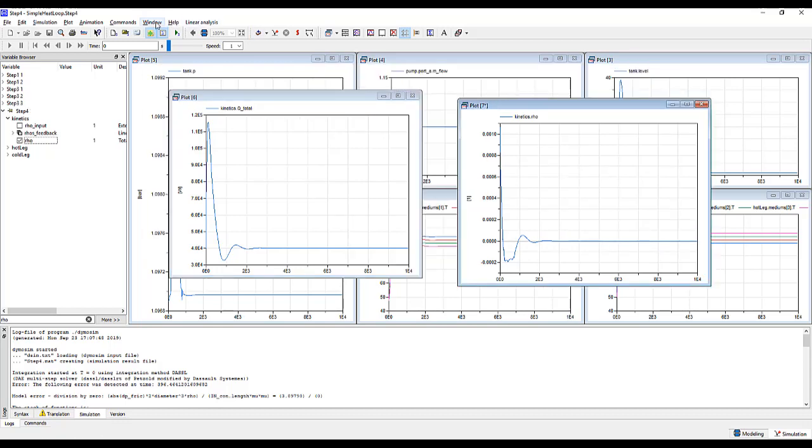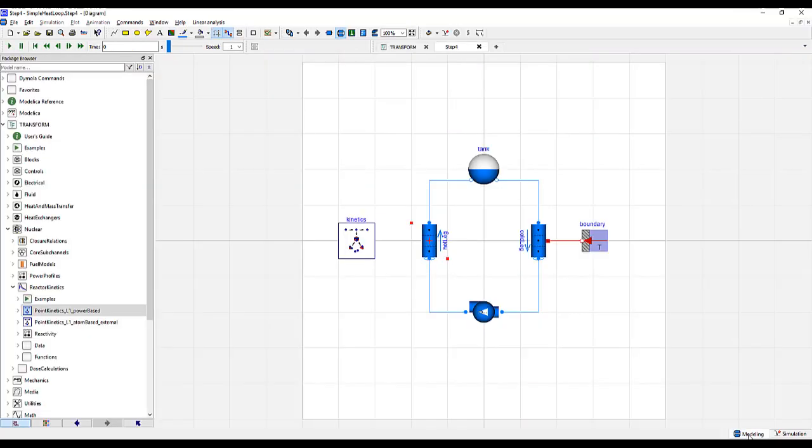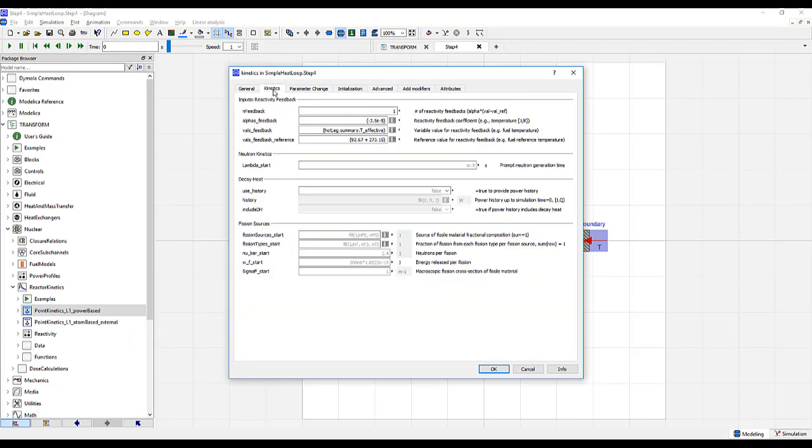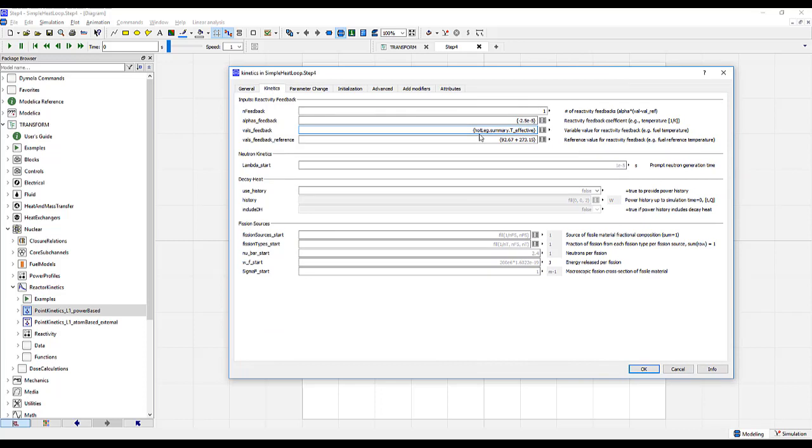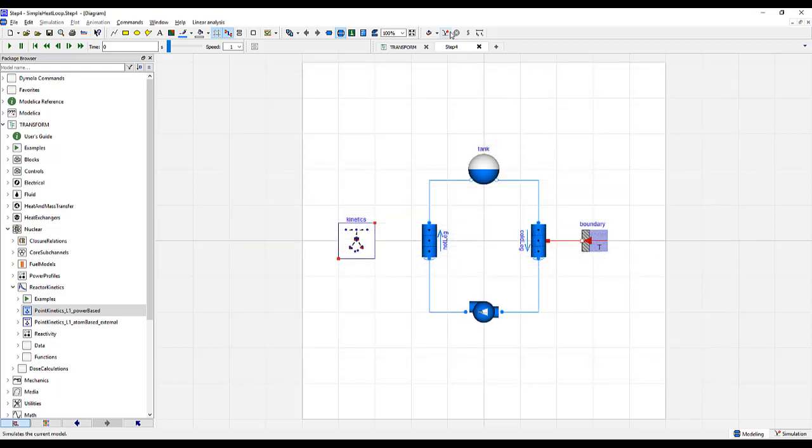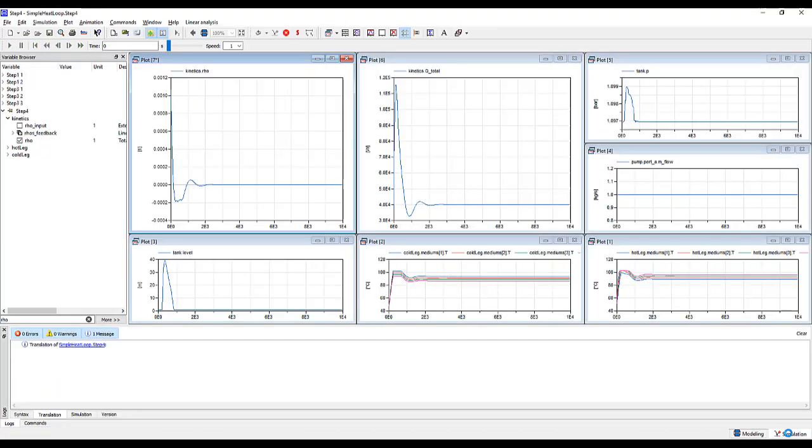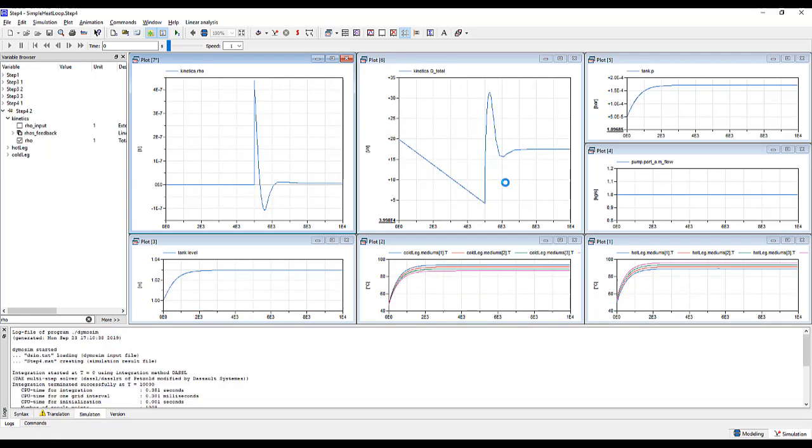Let's go ahead and correct for this. First, let's tile our windows so they look really nice again. Go to modeling, and let's go to kinetics. Here, we're going to do something a little tricky. To get around the spike in temperature, we are going to delay the feedback impact on the model until after the loop has gotten to an approximate steady state. For that, we can go if time is less than 5000, then we'll do kinetics.valsfeedback and take the first one. That's this right here. Else, the hot leg effective temperature. Click OK. Now we'll re-simulate. This is a much better result, much more along what we would expect.